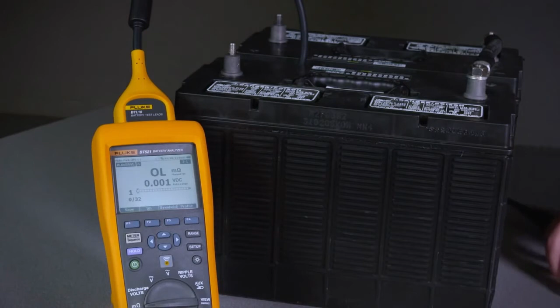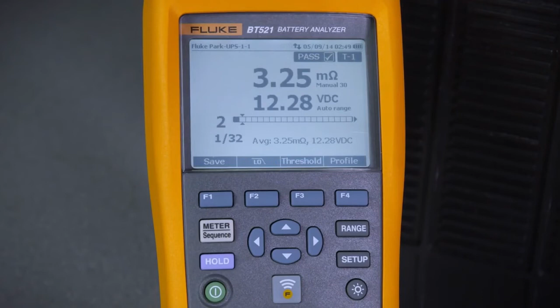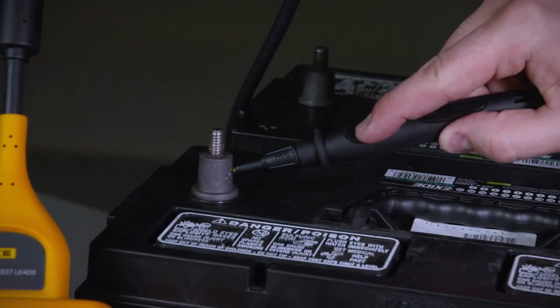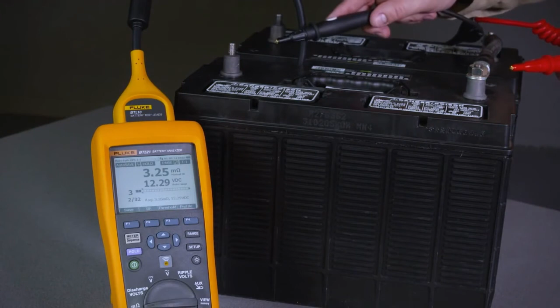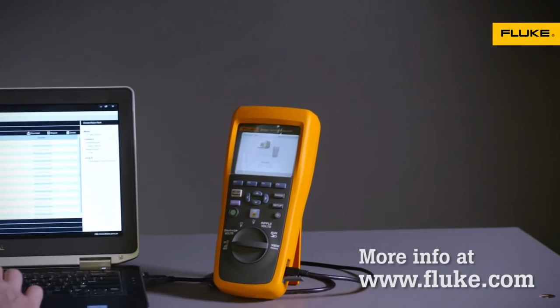As we connect the two probes, the instrument buzzes to confirm that it started the measurement and that the measurement is valid. Each time we remove the probe and make a new connection, the instrument automatically starts a new measurement. Each time you press the Save button on the probe, that measurement gets added to the sequence. Once we have all of our values in the memory, we can download them and create reports with the included battery analysis software.